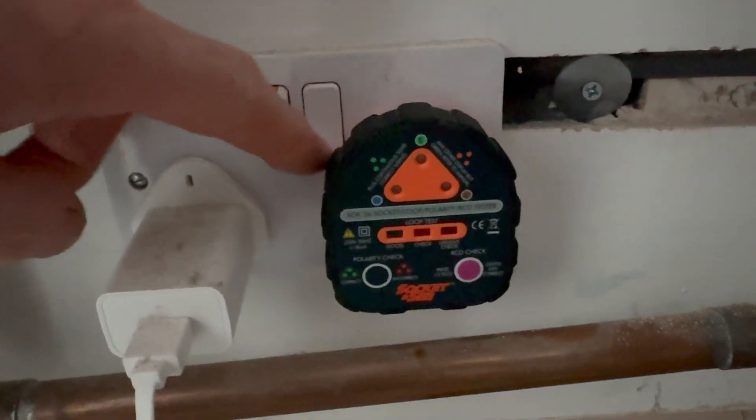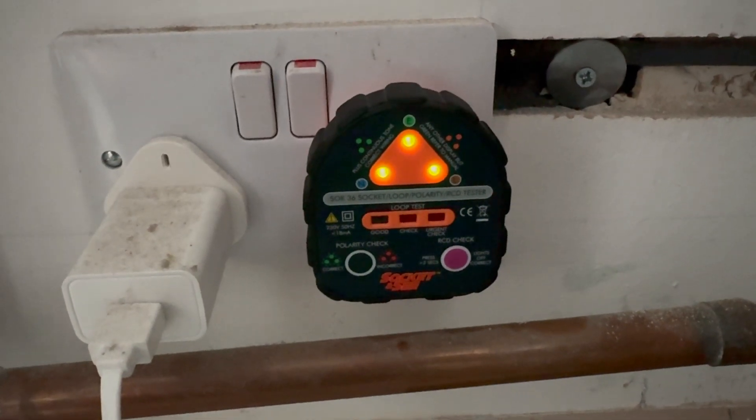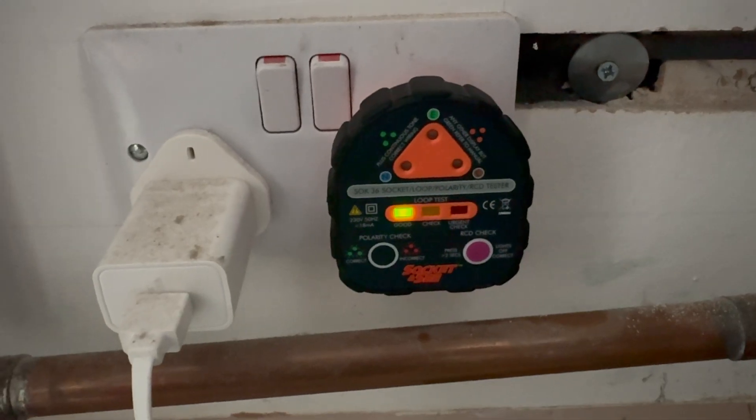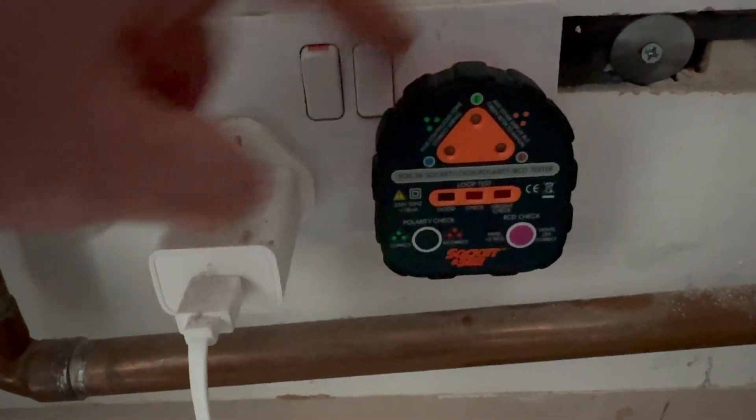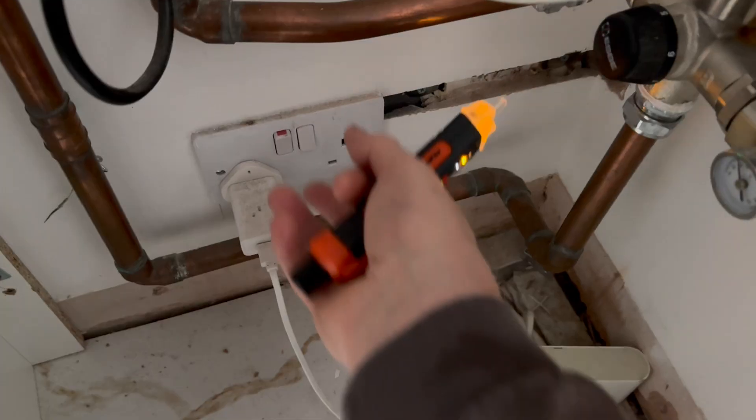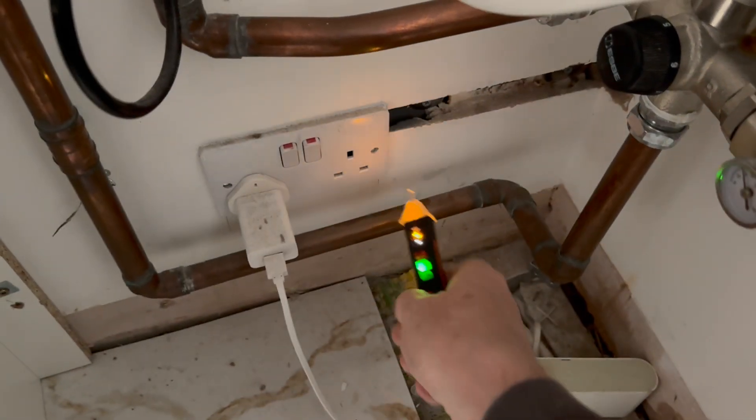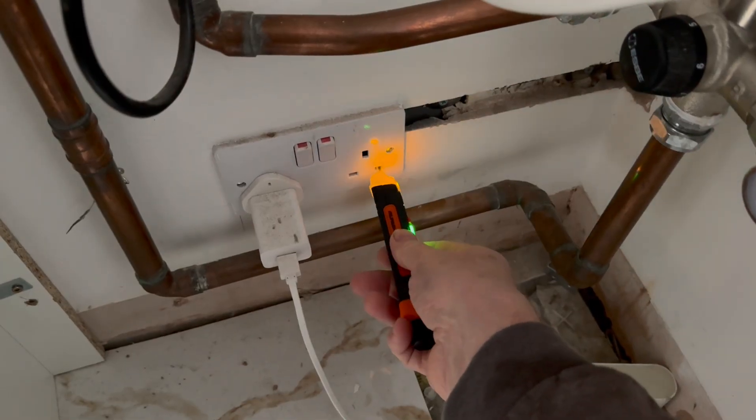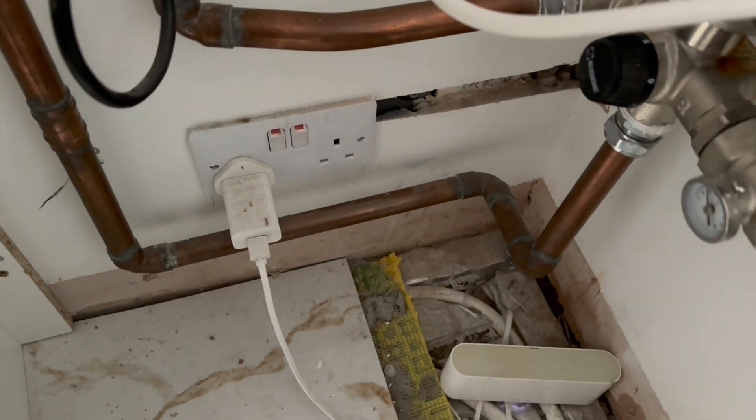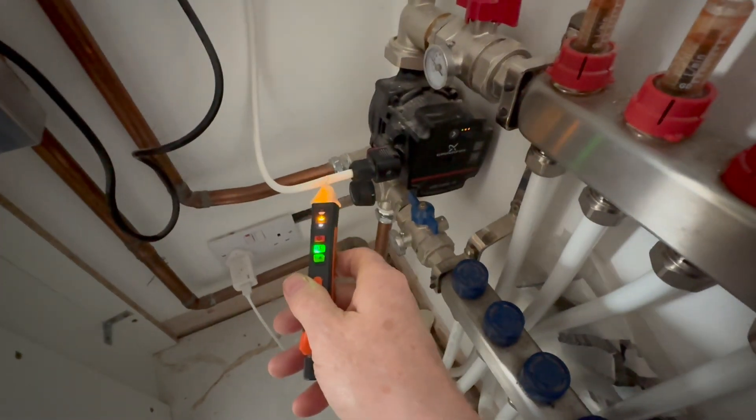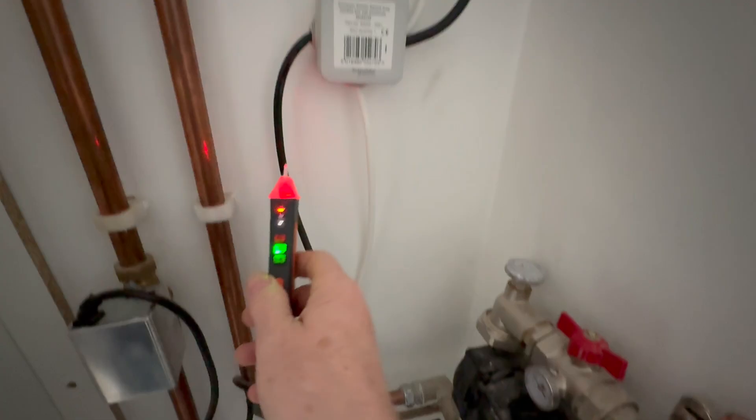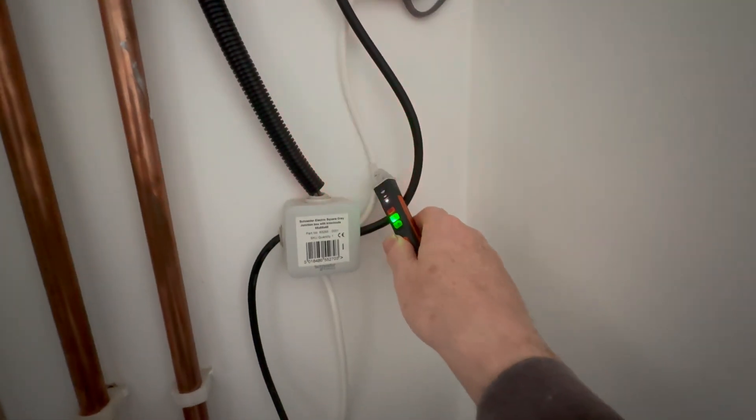I'm just using my Socket & See socket tester to make sure I've got polarity and earth loop impedance, which I have. Now I know this socket is live, I'm going to prove my non-contact voltage indicator to see if the power is actually on to all the wires. The pump's running, we've got power to the zone valve, power up to the stats, and power to the boiler.